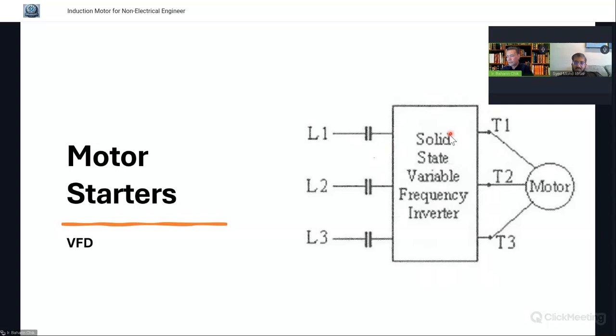Alright, understood. And the thermal protection from earlier, where does it sit here? It sits inside the VFD itself. Oh, I see. So it is part of the whole package. Everything is inside, so it will protect the motors, because it can measure. In the VFD it can measure current, voltage and power, and from there it makes a deduction, a calculation. And then the winding temperature also goes into the VFD, and it measures the overloading.